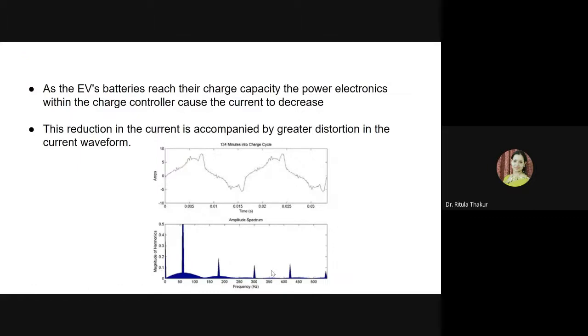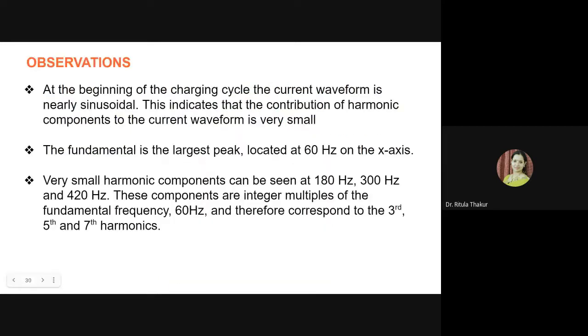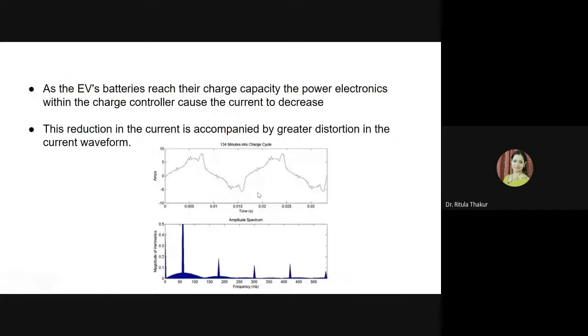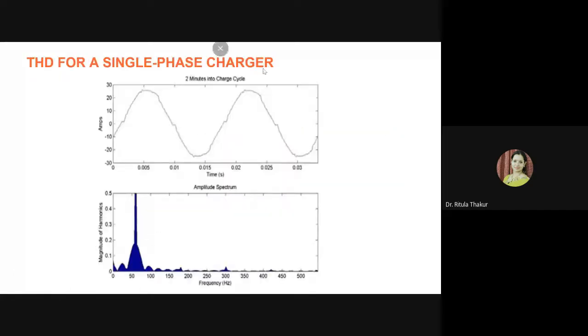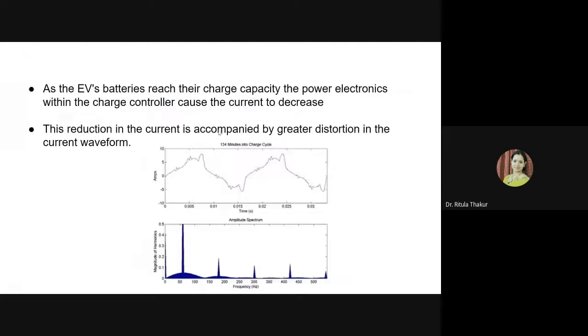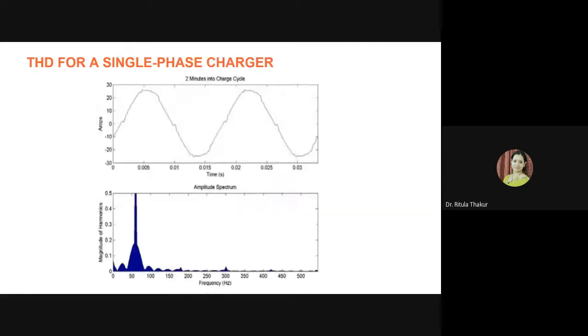But as the EV's batteries reach their charge capacity, the power electronics within the charge controller cause the current to decrease. So you can just compare this figure with this. This was initially 2 minutes into the charge cycle, whereas this is approximately 134, I mean, around 2 hours into the charge cycle, and you can see the waveform of the current has distorted. You can compare these harmonics also. You can see that the third, fifth, and seventh harmonics have become much more prominent as compared to here.